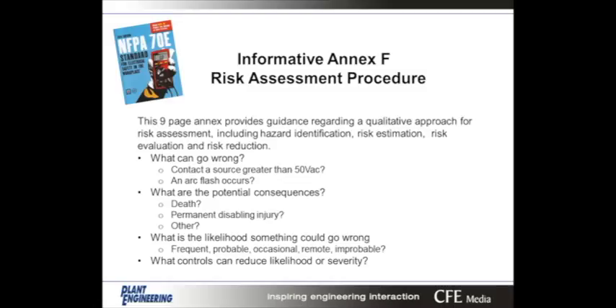But the 9-page annex provides guidance on an approach to risk assessment that includes hazard identification, risk estimation, risk evaluation, and risk reduction. It basically helps you answer these 4 questions. What can go wrong? And in particular, what can go wrong that could enable someone to contact a source greater than 50 volts AC or have someone exposed to an arc flash? Those are 2 things that can go wrong.